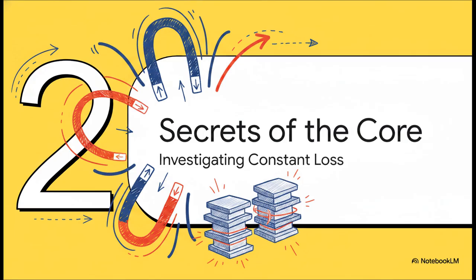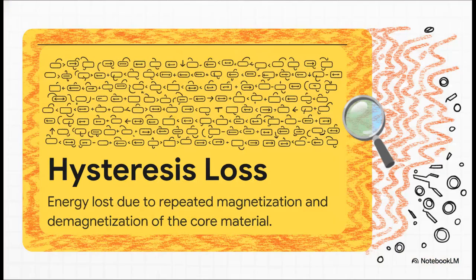Okay, so let's start with our first culprit, those constant, always-on losses. For this, we have to go deep inside the magnetic heart of the transformer, the iron core itself, to find the source of this persistent energy drain. The first type of core loss is called hysteresis loss. Just imagine the core is made of billions and billions of tiny, microscopic magnets. The alternating current forces all of them to flip back and forth, changing their polarity 50 or 60 times every single second. All that frantic flipping creates a kind of internal friction, and that generates heat. And that heat, that's wasted energy.